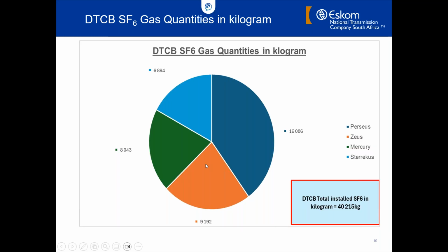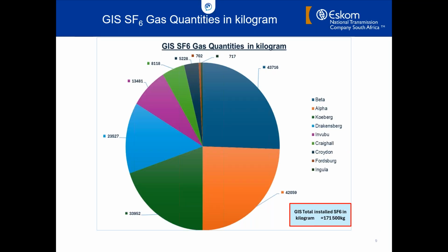Then on your dead tank circuit breakers, just to give you an indication of the amount of SF6 used there. That brings up our 40 tons or 40,000 kgs, 16 tons at one substation, 9 tons, 8 tons, and 6 tons. To give it a bit more perspective, if you look at the number of bays in those stations, for the GIS, if we look at a station like, for instance, Beta, there we're looking at 11 bays. There's only 11 bays, but they're contributing to 43,000 kilograms of SF6.